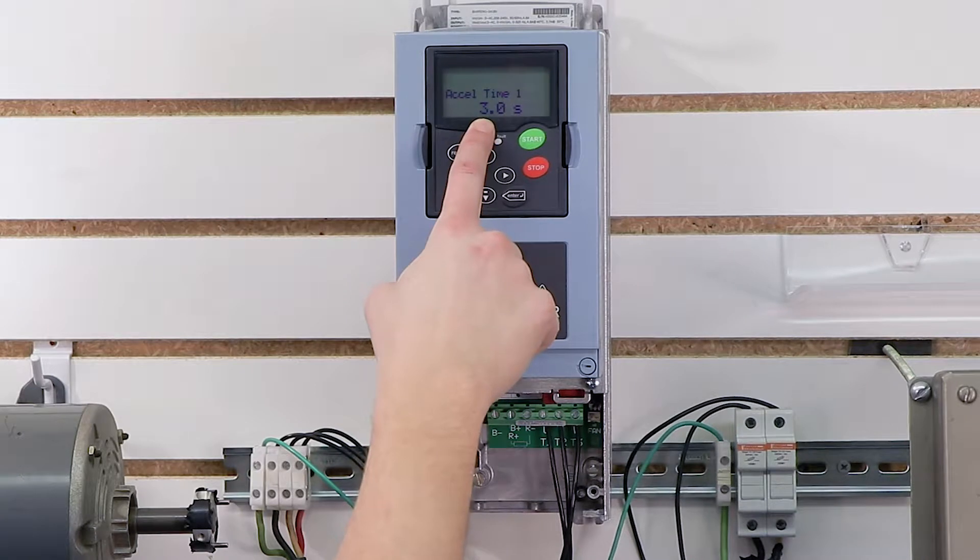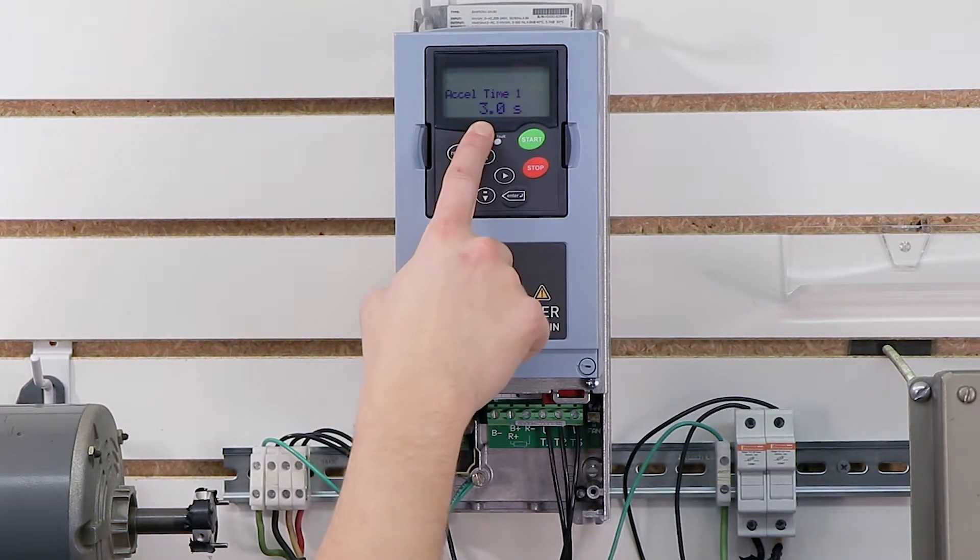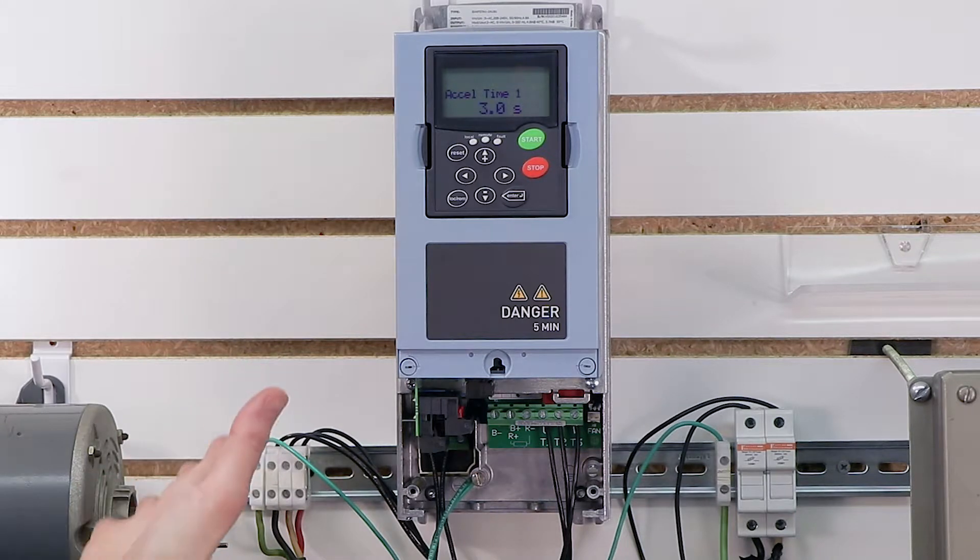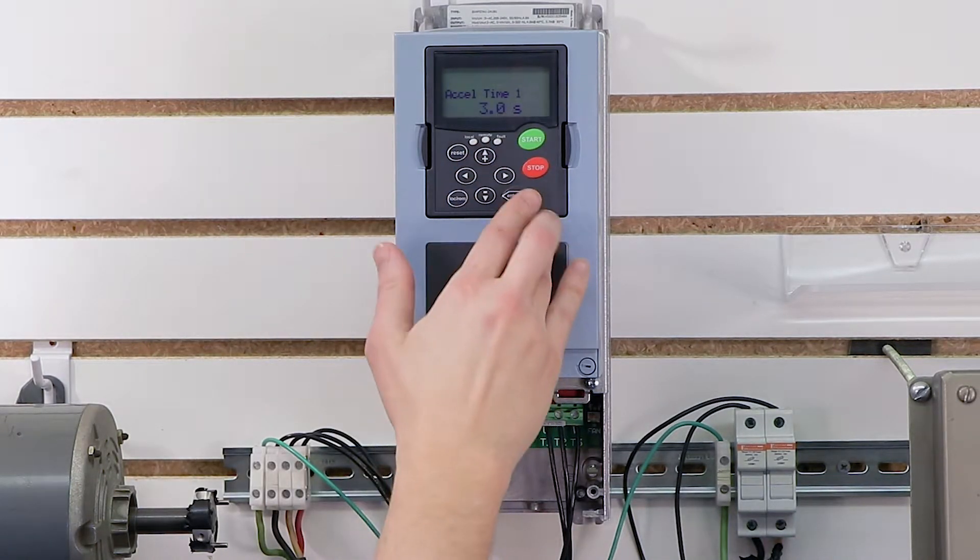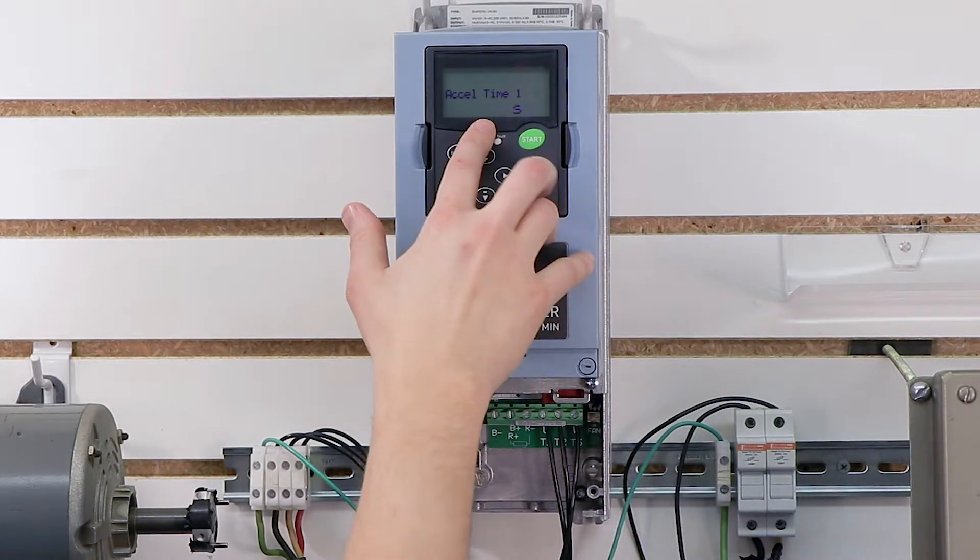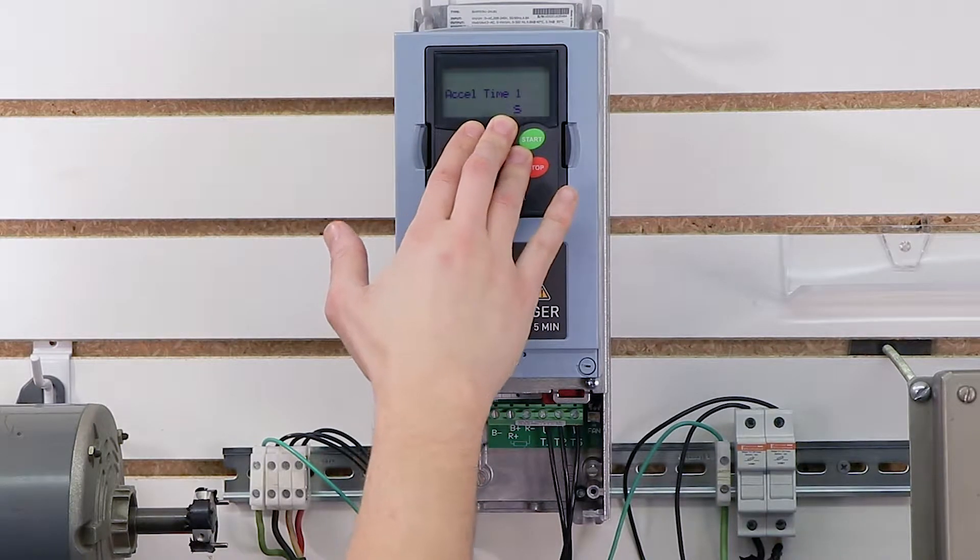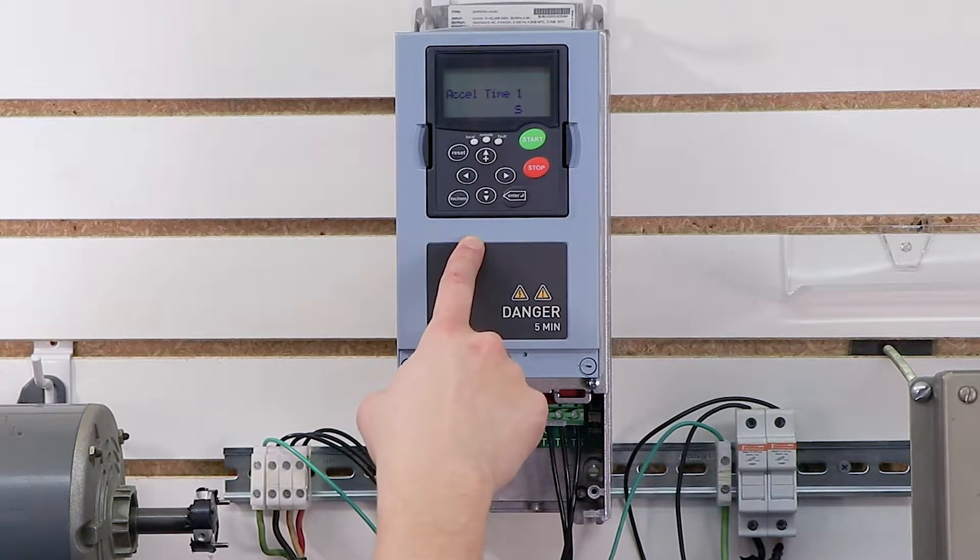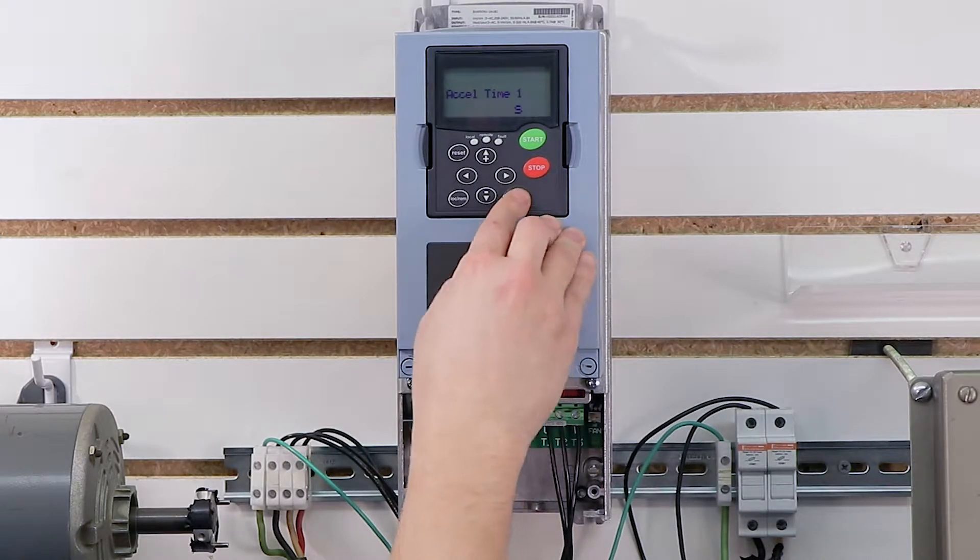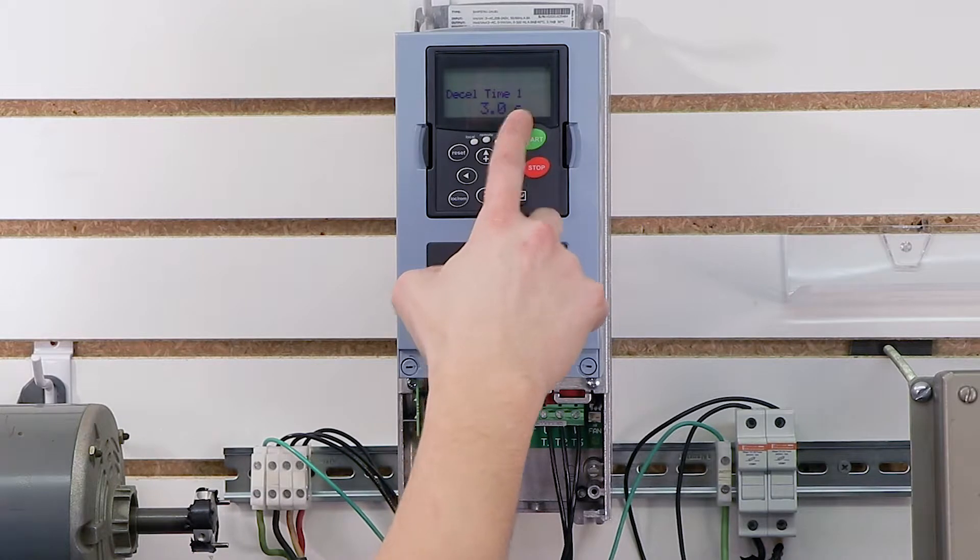For my acceleration time, the default is three seconds, which can be pretty aggressive for some applications. Obviously, I don't have my motor connected to a load, so three seconds is more than adequate. I could probably even do it faster. But for some people, if you're not sure how much of a load or how aggressive your load is, you can start this at a default 20 seconds or even 60 seconds just to see how your load responds. And you can always go in and change it later. So I'm going to press enter on three seconds for accel and then decel time comes up.